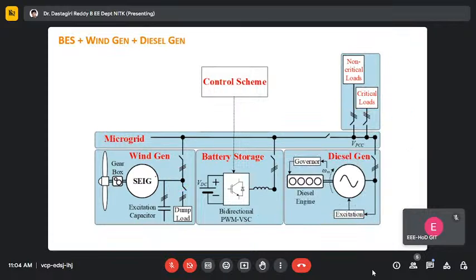So another mode: when you have wind generation, battery and diesel, what can you do? I can ask the diesel generator to make the grid. The PQ will be here, and this will also run in PQ. But there is no power electronic converter here, so basically this can be regarded as a weak grid, and it just follows once it is synchronized to a strong grid.